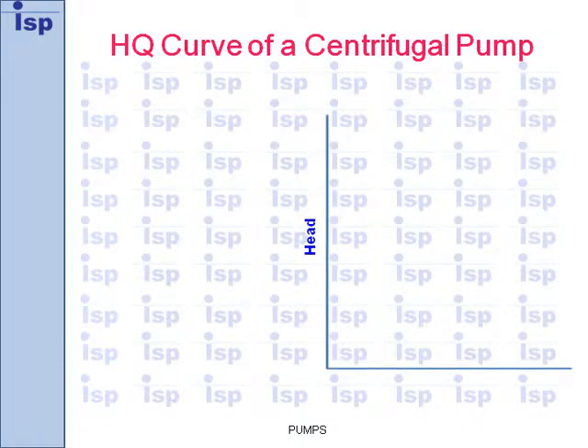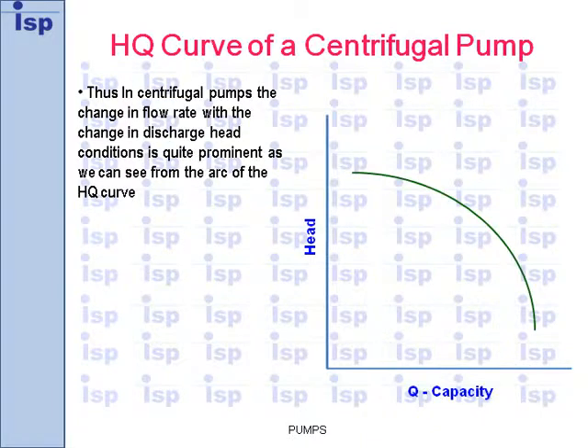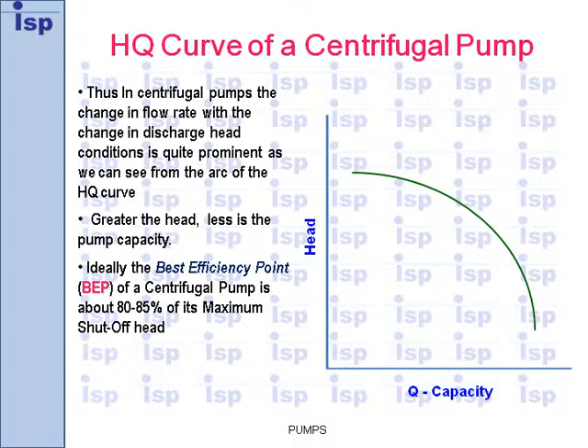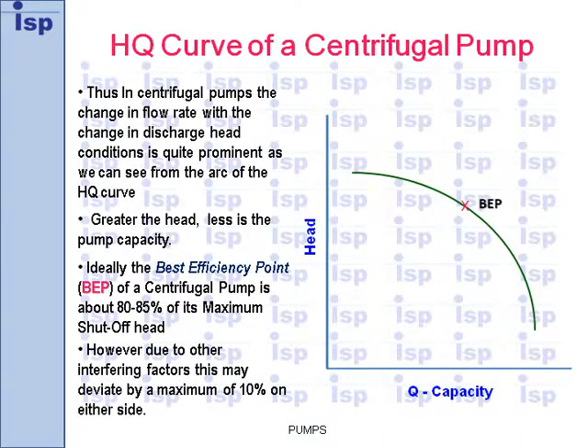Head versus capacity. Thus, in centrifugal pumps, the change in flow rate with the change in discharge head conditions is quite prominent, as we can see from the arc of the HQ curve. Greater the head, less is the pump capacity. Ideally, the best efficiency point of a centrifugal pump is about 80–85% of its maximum shut-off head. However, due to other interfering factors, this may deviate by a maximum of 10% on either side.